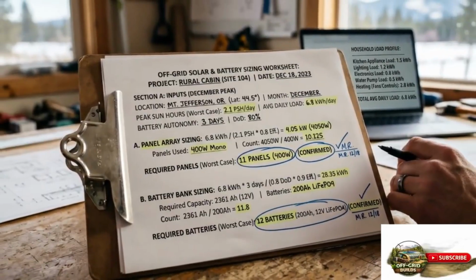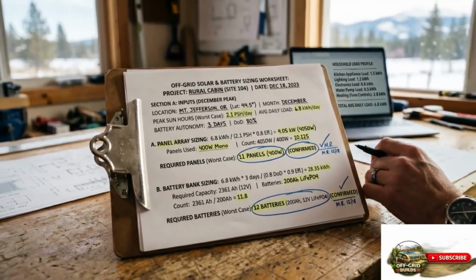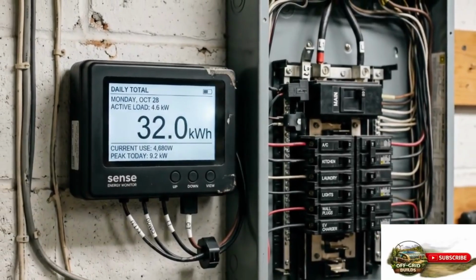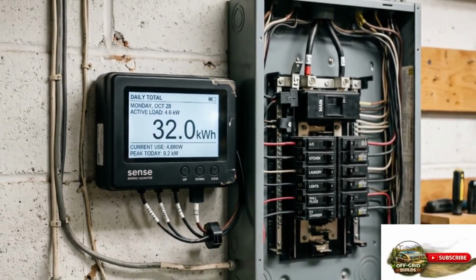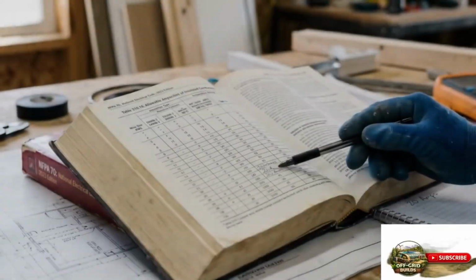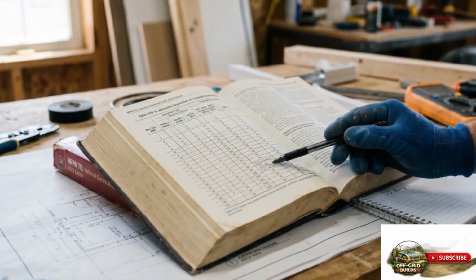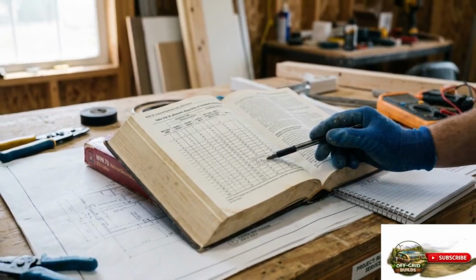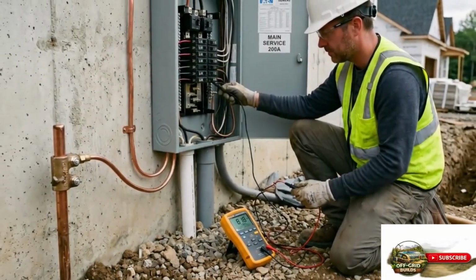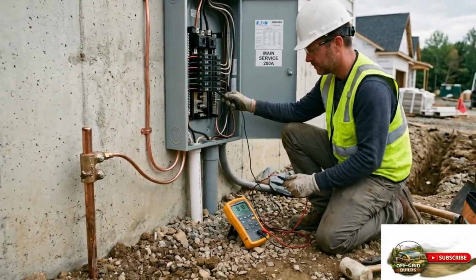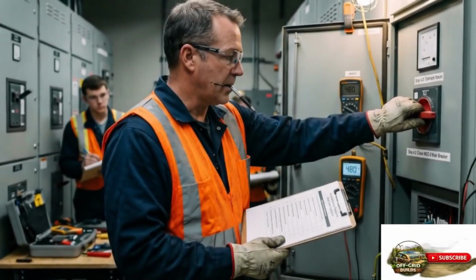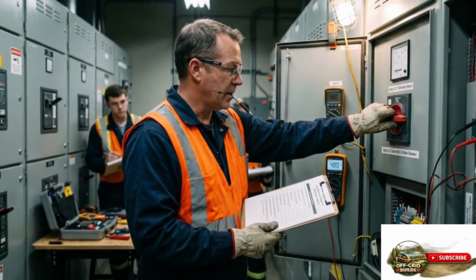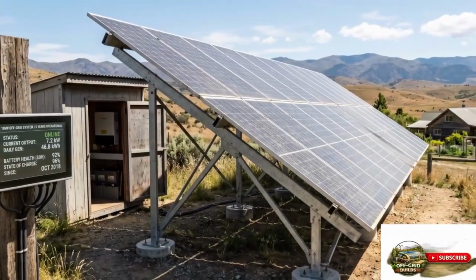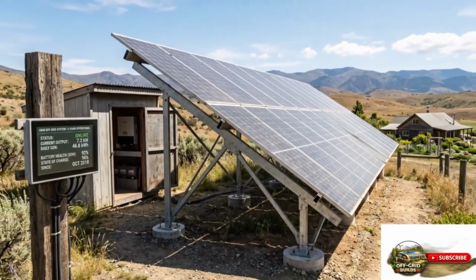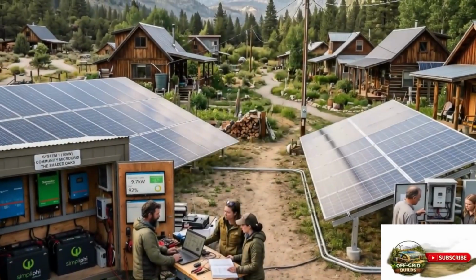Size for worst-case conditions. Use worst-month solar resource data from a reliable source. Measure your actual household loads rather than estimating them. Choose battery chemistry and capacity that provides adequate autonomy for your climate and your lifestyle. Wire every circuit to the appropriate standard. Ground the system correctly. Commission it methodically. Do those things and you have an off-grid solar system that does exactly what you built it to do for 20 to 30 years, producing free electricity from sunlight and giving you the energy independence that a grid-tied household can never fully achieve.